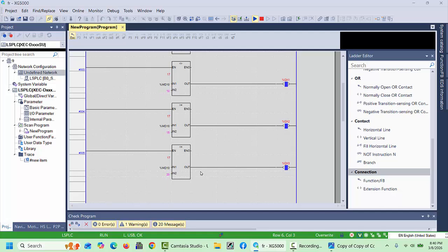And this is QX3, which defines less than 20 or equal with 20, so the output will be on at 18, 19, 20. As the signal increases to 21, the output is now off. And as I give the signal at IX1, QX3 and QX1 will continue to be on, because this is the less than or equal, and this is the not equal command.